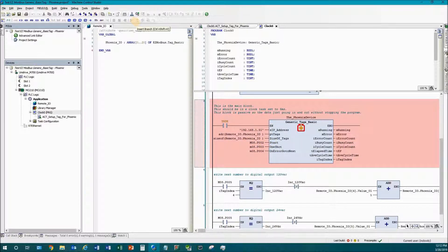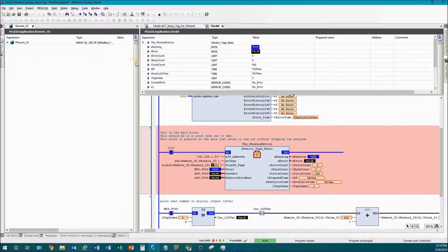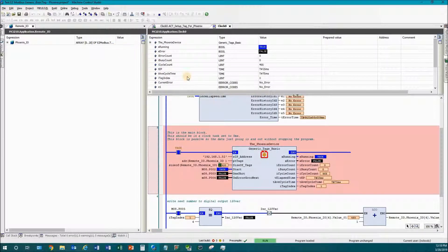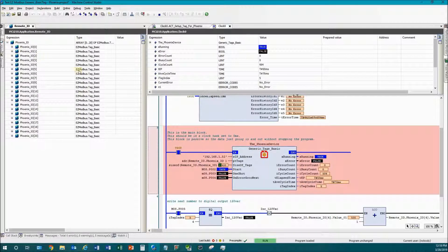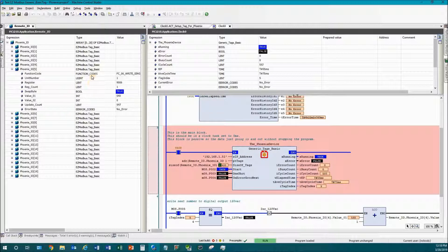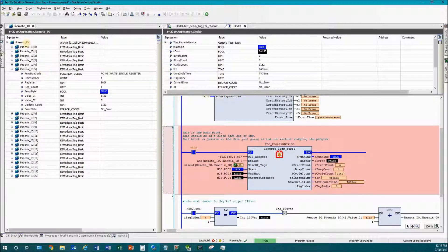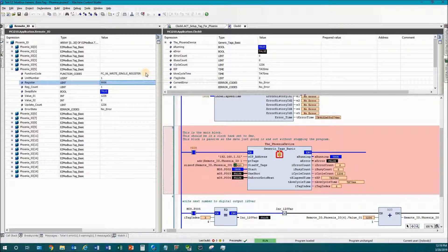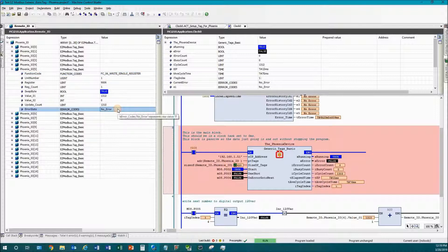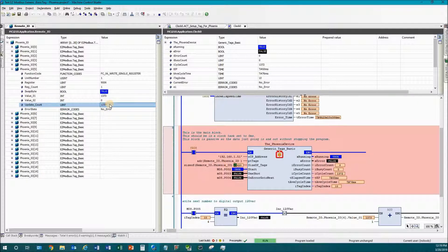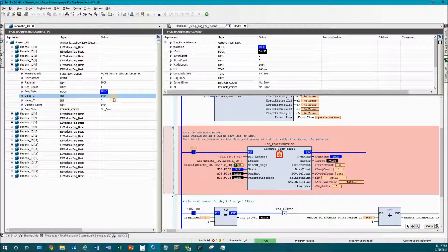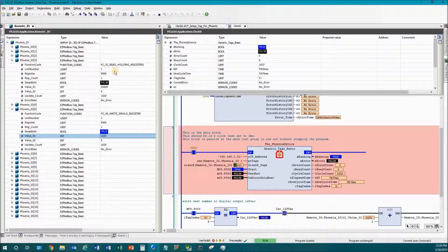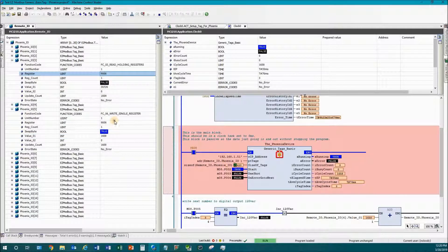Alright, so now I'm online. I'm going to minimize some of this so we can see more what I want to see. On the left side I have my data tags. Now I can expand it and I'm going to look at number five, or you could say six tag in my array of tags here. It's pointed to 9006 and you can see I got it set to write a single register and there are no errors. This little number here tells you how many times that we've actually done this action, and here's the actual live value that we're writing.